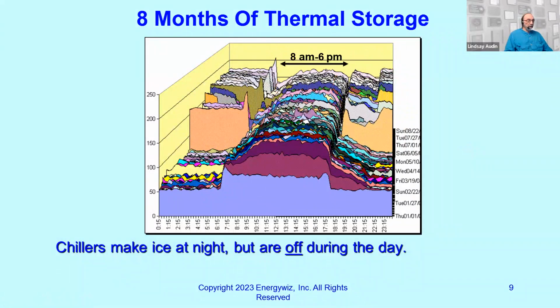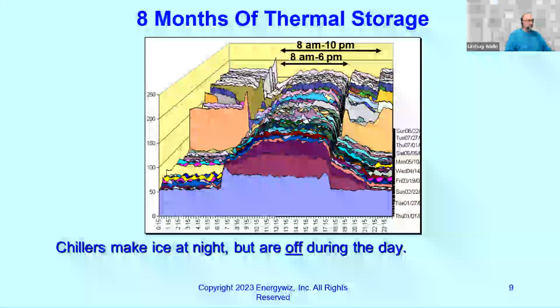Notice how they operate their building. Very good, tight control. 8 a.m. to 6 p.m., that period in the peak demand charge, they cut off the thermal storage right before 8 a.m. They reduce and shut off everything else in the building they can at around 6 p.m. After that, they turn on 1 or 2 chillers until it gets to about 10 p.m. and then they turn on the third one. And that, of course, wraps around to the midnight of the next day. So they have designed and tried to control their loads around the tariff to minimize their peak loads.